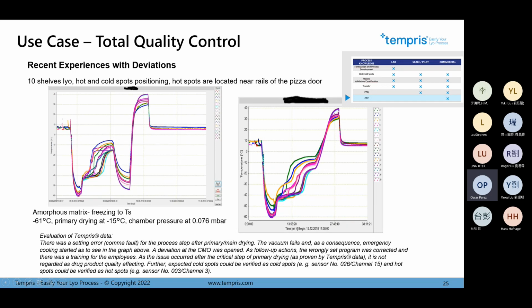the vacuum breaks, and the product starts freezing. But thanks to the measurement of the temperature, we can confirm the product was completely dry at this point when the freeze dryer vacuum failed. So, reporting to the authorities with these temperature values, we can help a lot and reduce time and effort to confirm that the batch or the product stays in good condition.